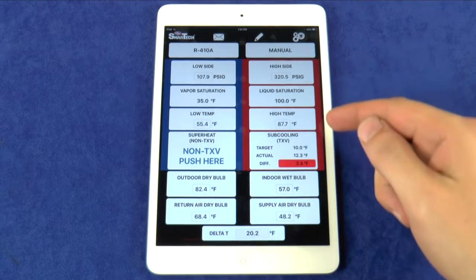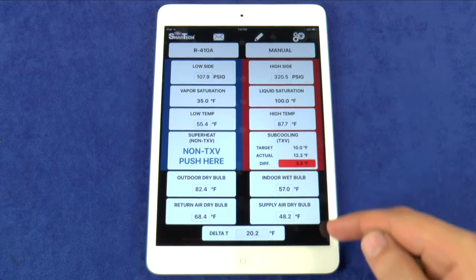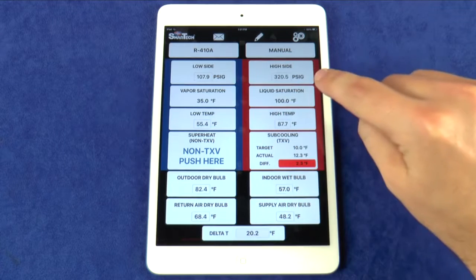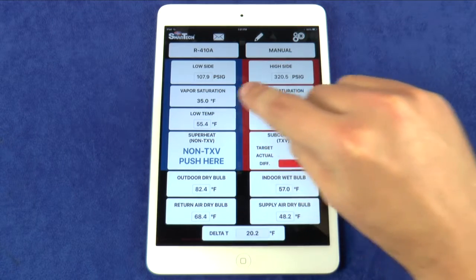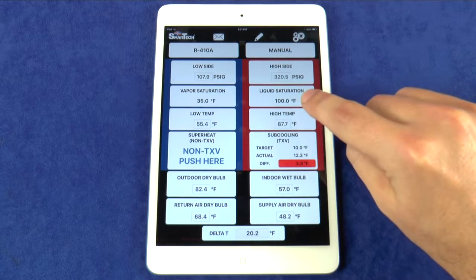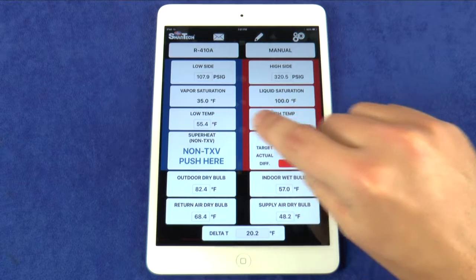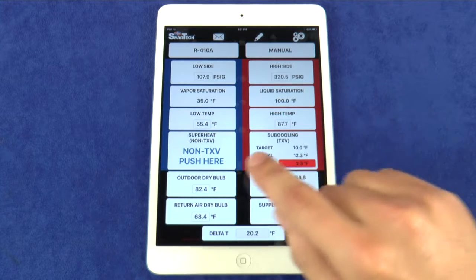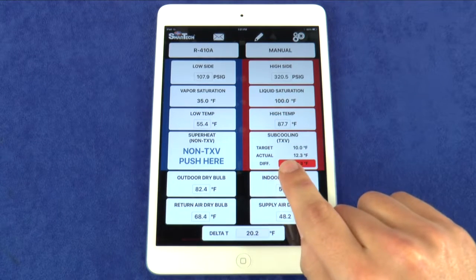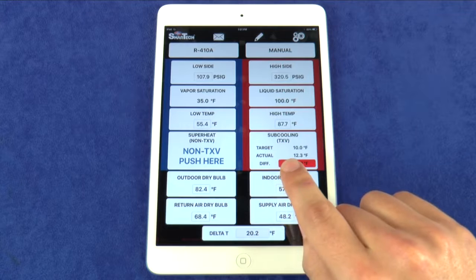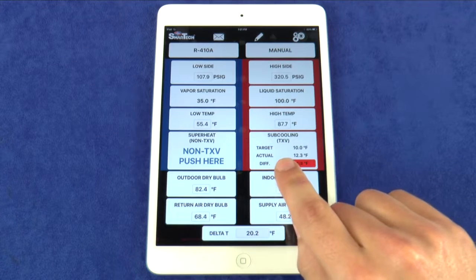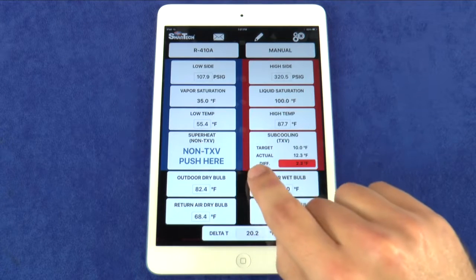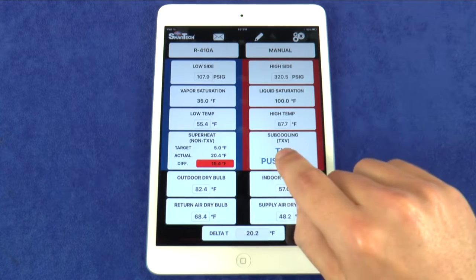This is where all of the system readings are displayed. Here we see the low side pressure and high side pressure, vapor saturation and liquid saturation, low side temperature and high side temperature. Superheat and subcooling calculations are done automatically and show here. You can easily toggle between superheat and subcooling by pressing either one.